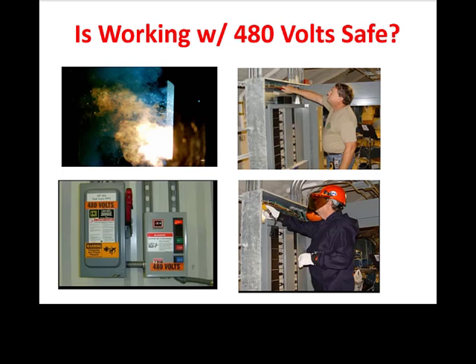An arc flash occurs extremely fast, with most lasting less than a fraction of a second for 480 volts or greater. The duration depends on the clearing time for the circuit breaker or fuse to trip and shut off power. The age and condition of the overcurrent protection devices also has an effect on the clearing time. For an aging breaker that has never operated or been maintained, it may not open the circuit, and the upstream overcurrent protection device will have to operate to shut the power off.